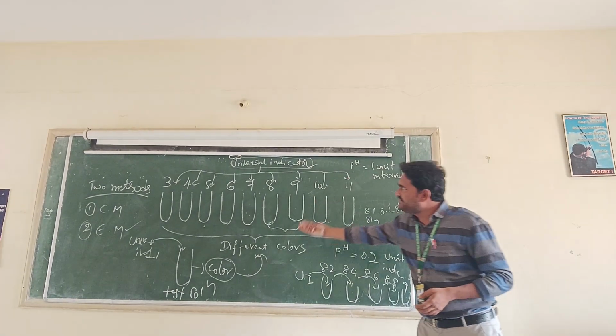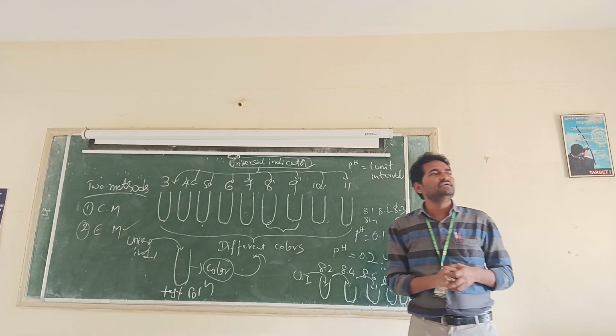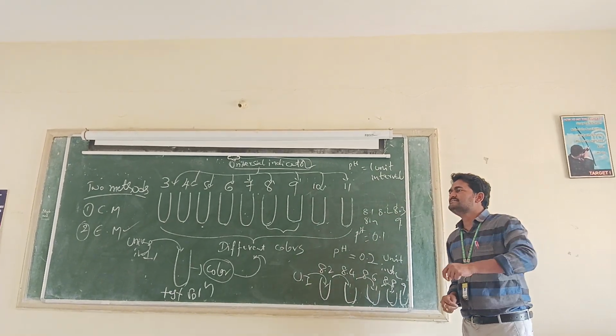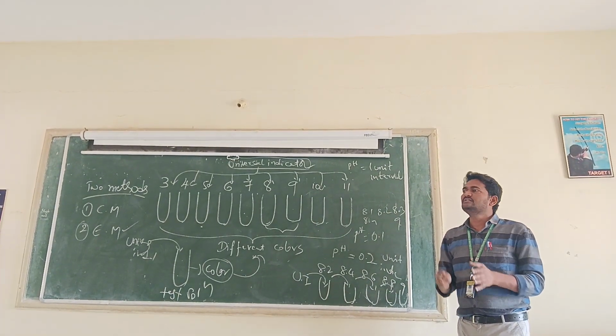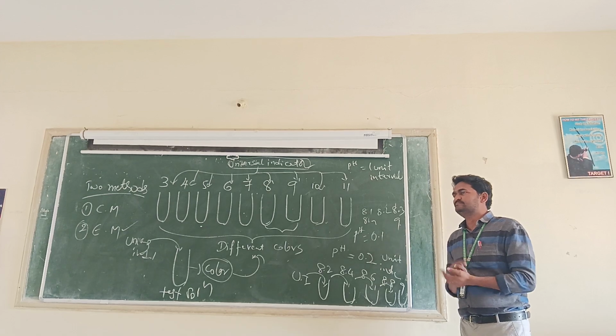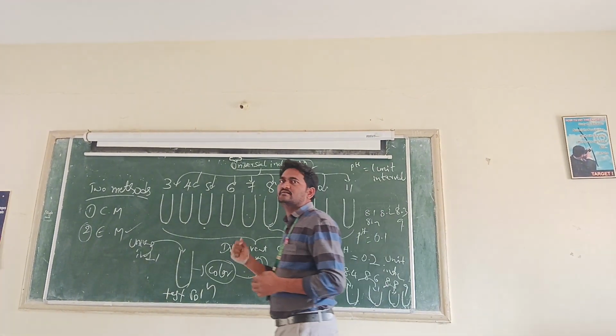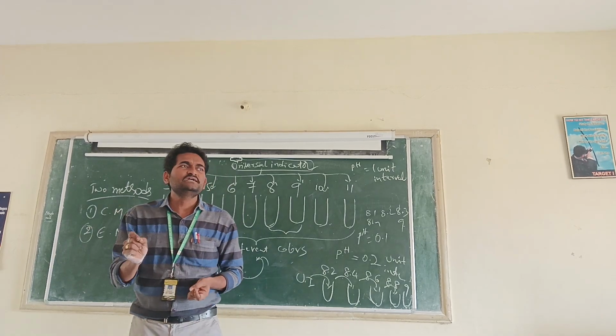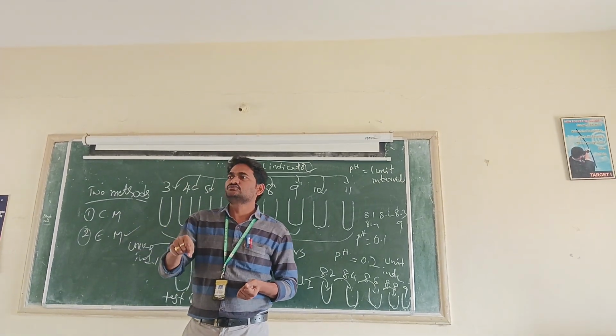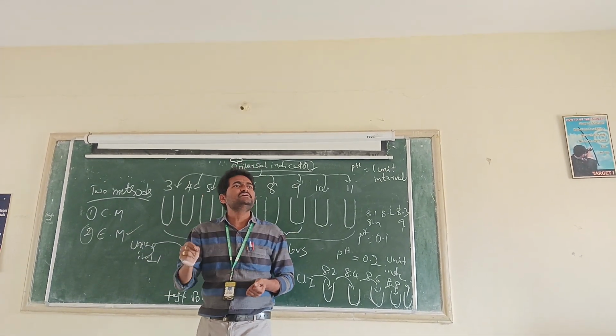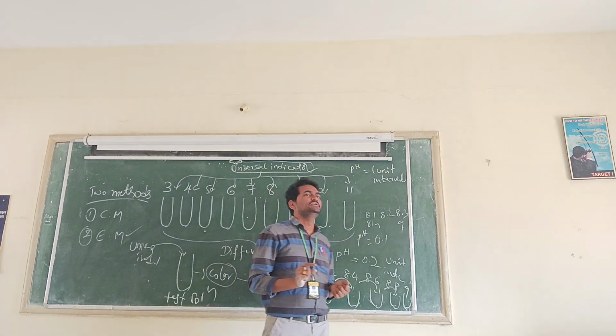Similar to the colorimetric method, here also we immerse the glass electrode in a known standard buffer, such as standard buffer 4, 6 or 8. We check whether the glass electrode shows the same pH on the readout device or not.